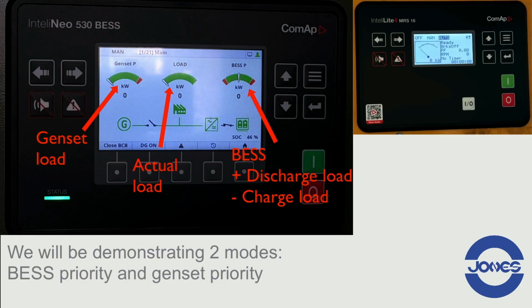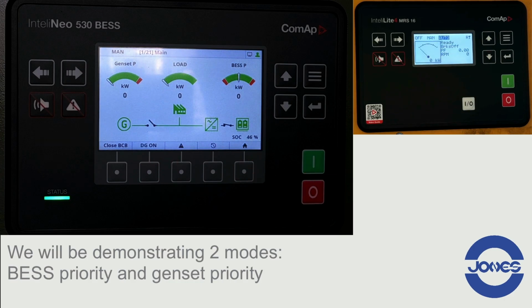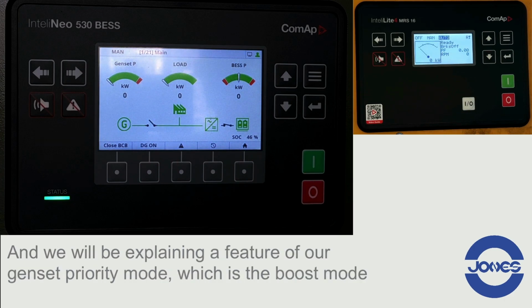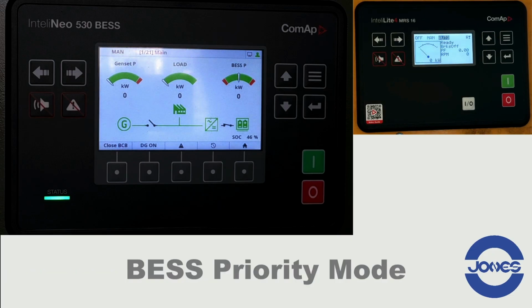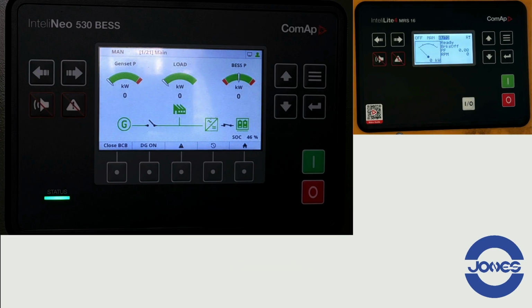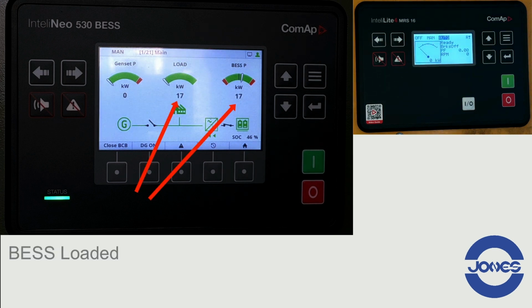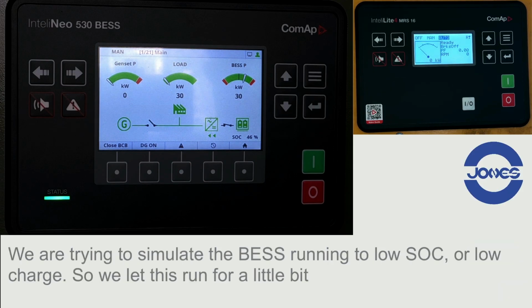We will be demonstrating two modes: BESS Priority and Genset Priority. And we will be explaining a feature of our Genset Priority mode, which is the boost mode. BESS Priority mode. The BESS is loaded. We are trying to simulate the BESS running to low SOC, or low charge, so we let this run for a little bit.